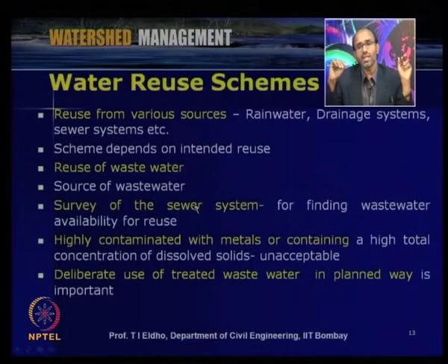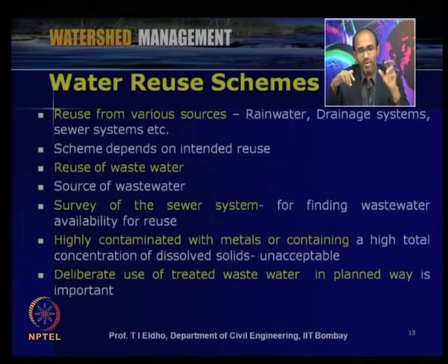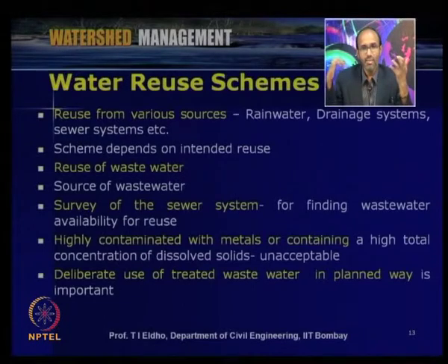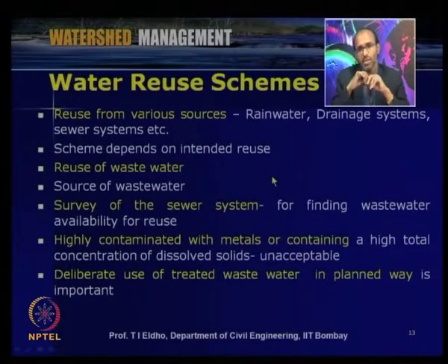So when we look into wastewater reclamation and reuse, in a particular area we have to study the system and the quality of the wastewater coming. We have to collect samples from the various sewer systems and identify the parameters within that wastewater before going for the appropriate treatment. Highly contaminated wastewater with metals or containing a high concentration of total dissolved solids is generally unacceptable for most uses, especially domestic or industrial purposes.